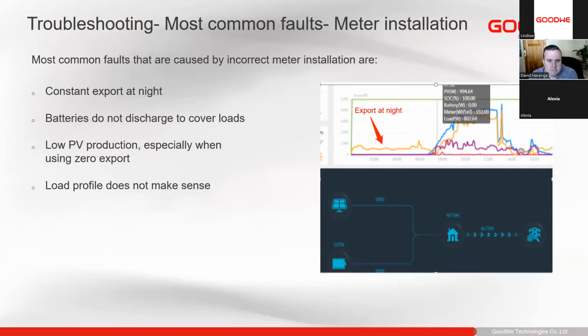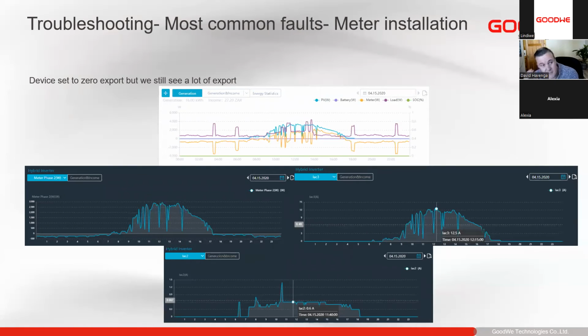So here's an example, as I said, with the phase order fault. This is a 3-phase system. This customer set it to 0 export, so they're not allowed to export to the utility because they will be billed where they are exporting. Yet we can see on the main graph there is quite a bit of export happening, although it's set to 0 export. But because we have our ETs, they do have the unbalanced output, so it's set to unbalanced output.